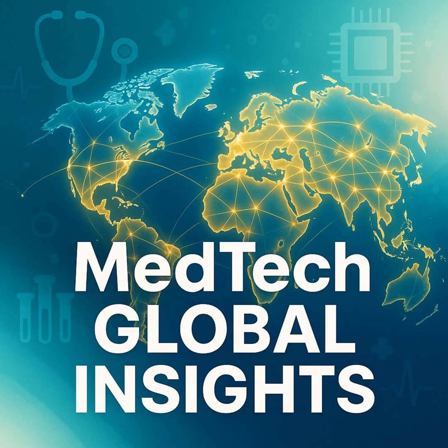A real-world example involves a diagnostic imaging software. The company described its algorithm using marketing-friendly terms like "revolutionary" and "unparalleled accuracy" instead of precise technical specifications. The FDA issued a refuse to accept letter simply because the claims were not substantiated with objective technical language and data. Your submission is a technical and legal document, not a marketing brochure. Clarity, precision, and consistency are paramount.